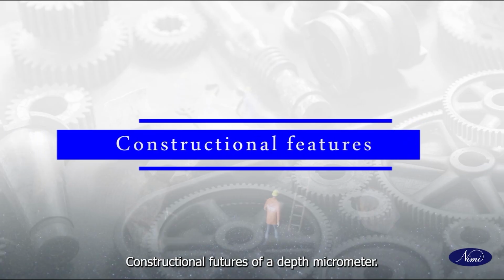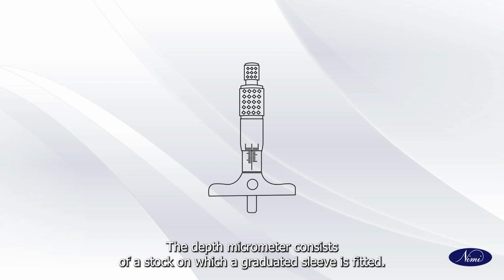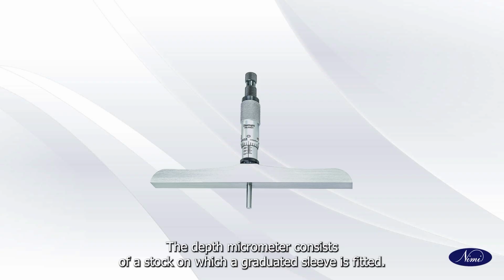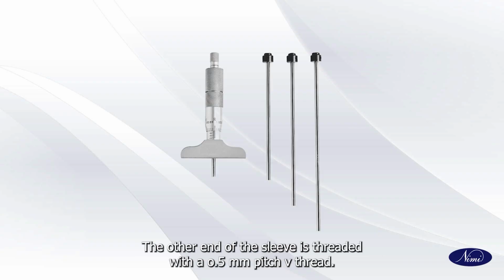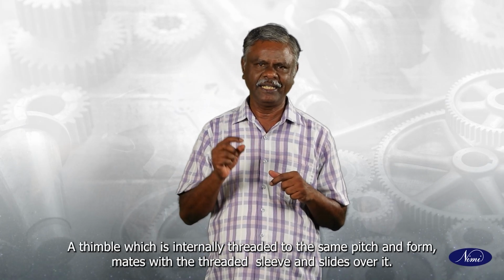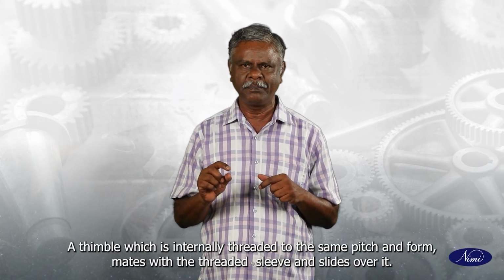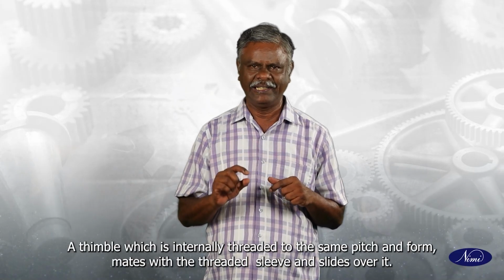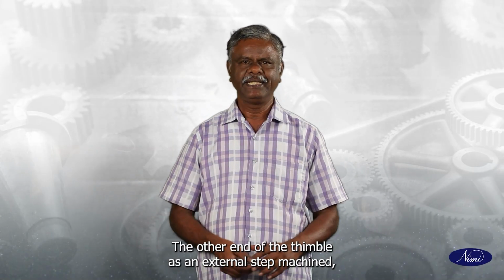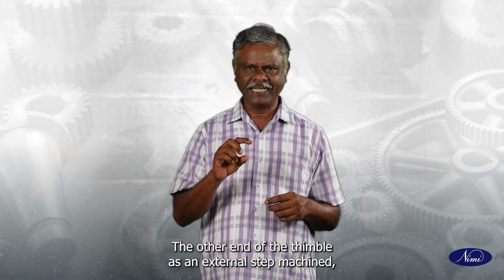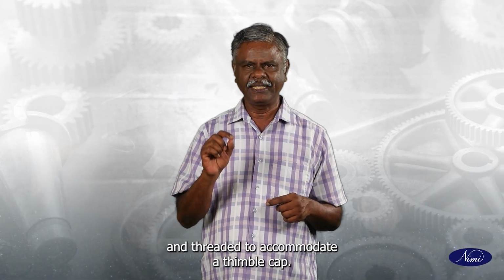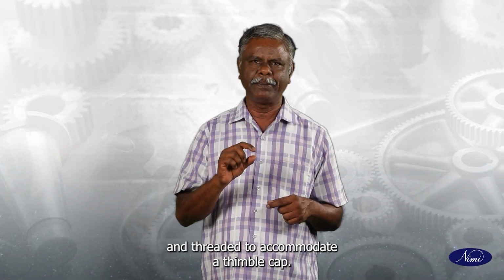Constructional features of a depth micrometer. The depth micrometer consists of a stock on which a graduated sleeve is fitted. The other end of the sleeve is threaded with a 0.5 mm pitch V thread. A thimble which is internally threaded with the same pitch and form mates with the threaded sleeve and slides over it. The other end of the thimble has an external step machined and threaded to accommodate a thimble cap.